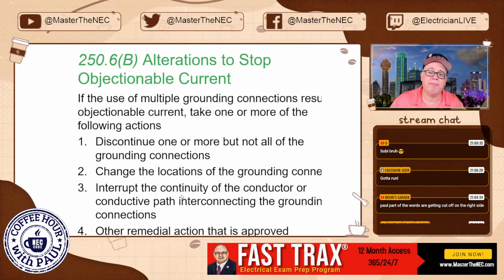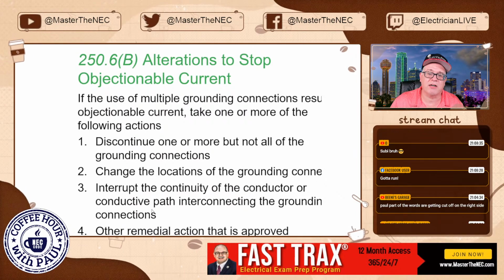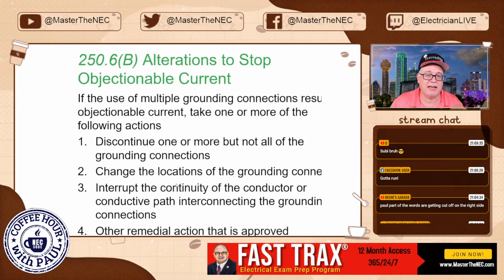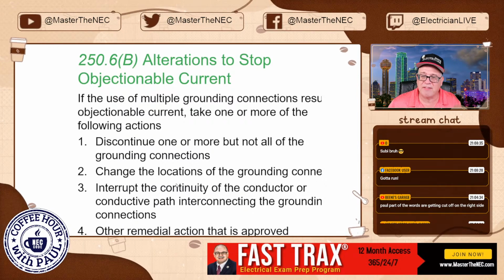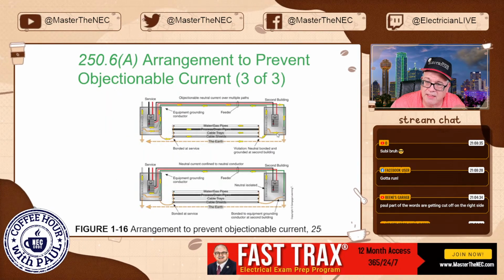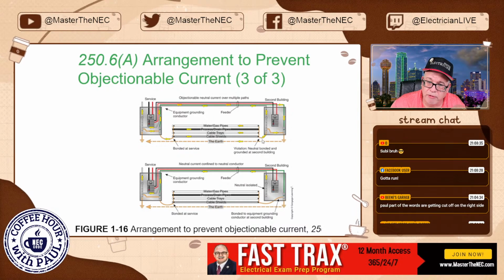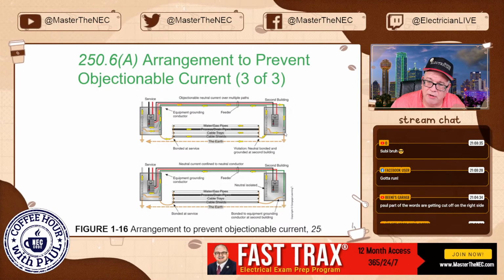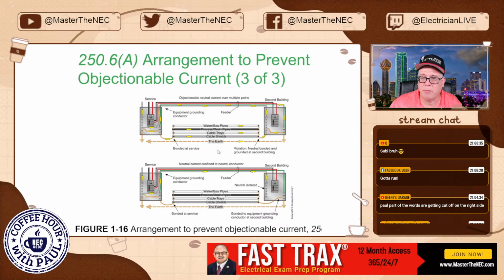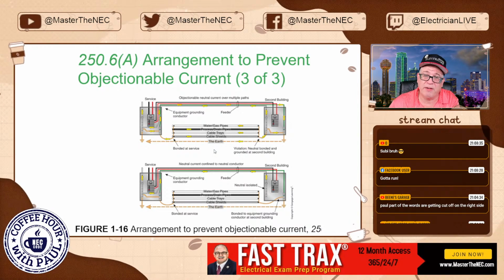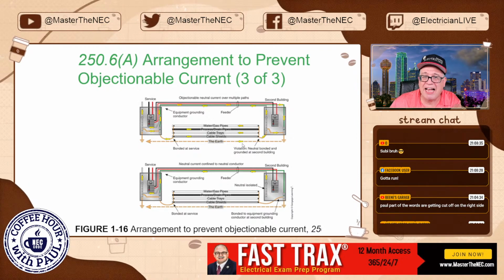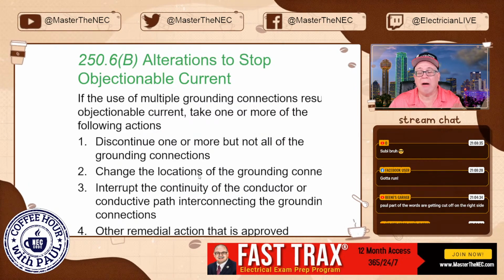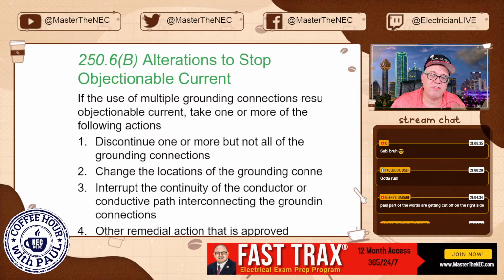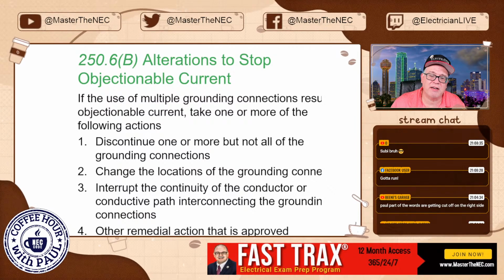It says interrupt the continuity of a conductor or conductive path interconnecting the grounding connections. Might have to take, now in this example, take this off. Reroute this conductor over here. Get rid of this main bonding jumper because it is a remote distribution panel. And this is a violation of 250.24(A)(5). So that's a procedure I would have done. And then, of course, it says other remedial action that is approved.